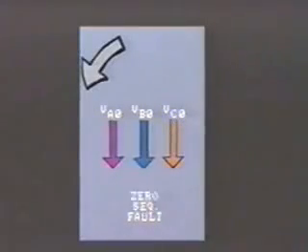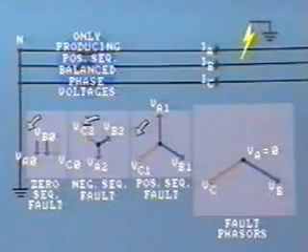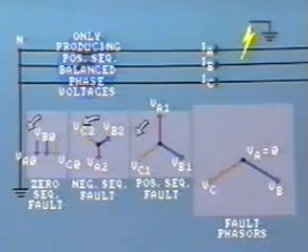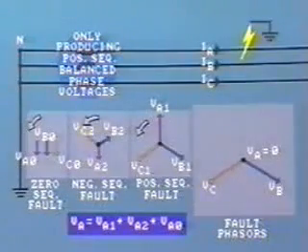Another interesting factor becomes apparent. The V0 components in each of the phases are of identical magnitude and all are at the same phase angle. In fact, these voltage components have no sequence at all — so they are called zero sequence components. To review, to get each phase voltage at the fault, we add the three components together. For example, VA equals VA1 plus VA2 plus VA0.